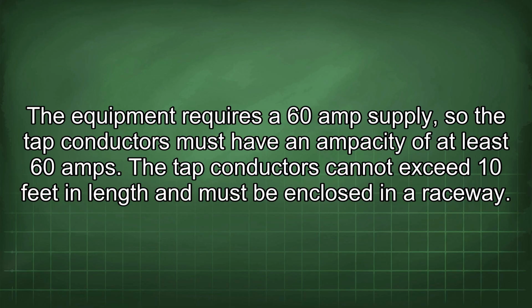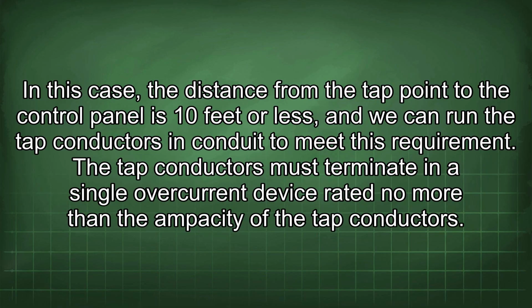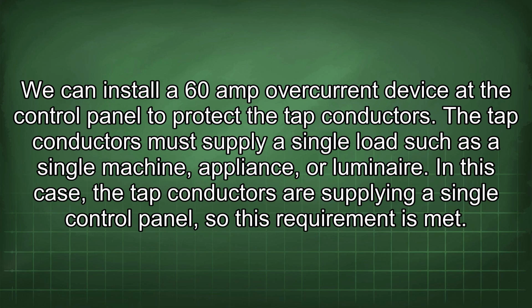The tap conductors cannot exceed 10 feet in length and must be enclosed in a raceway. In this case, the distance from the tap point to the control panel is 10 feet or less, and we can run the tap conductors in conduit to meet this requirement. The tap conductors must terminate in a single overcurrent device rated no more than the ampacity of the tap conductors. We can install a 60 amp overcurrent device at the control panel to protect the tap conductors. The tap conductors must supply a single load such as a single machine, appliance, or luminaire. In this case, the tap conductors are supplying a single control panel, so this requirement is met.